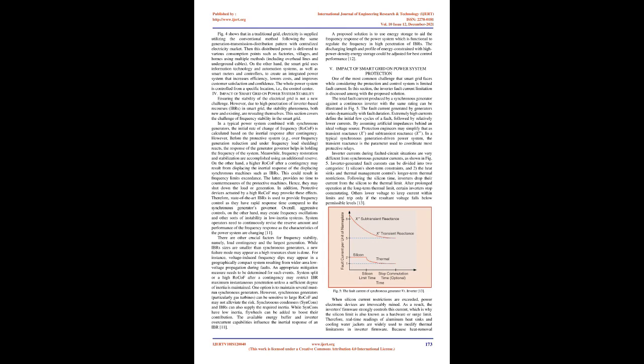System operators need to continuously revise the reserve amount and performance of the frequency response as the characteristics of the power system are changing. 11. There are other crucial factors for frequency stability, namely, load contingency and the largest generation. While IBR sizes are smaller than synchronous generators, a new failure mode may appear as a high resources share is done. For instance, voltage-induced frequency dips may appear in a geographically compact system resulting from wider area low voltage propagation during faults. An appropriate mitigation measure needs to be determined for such events.